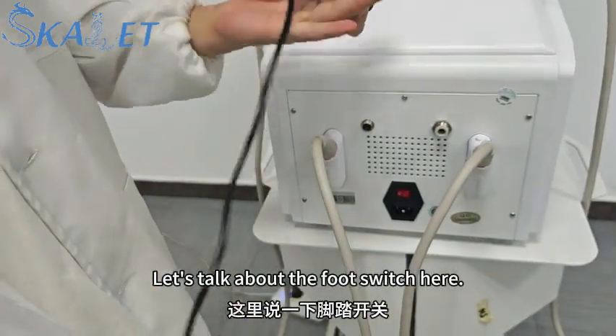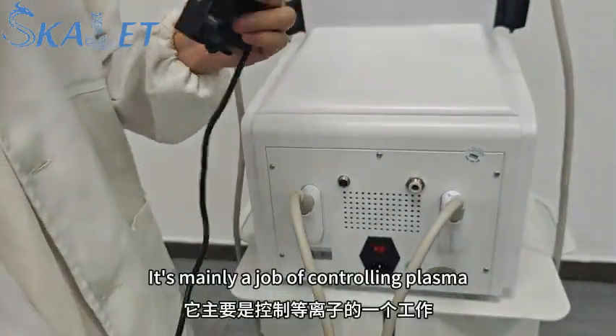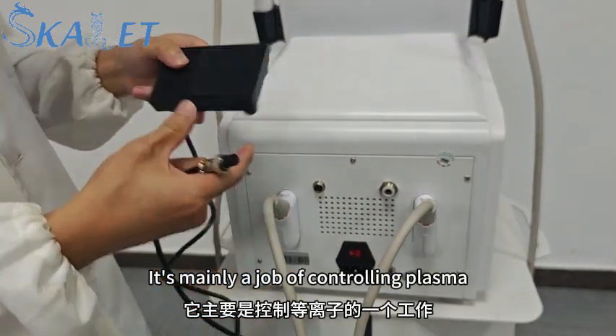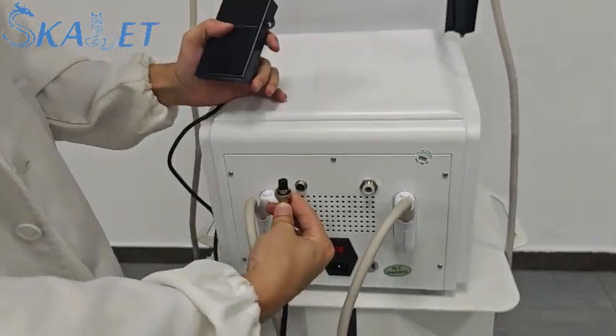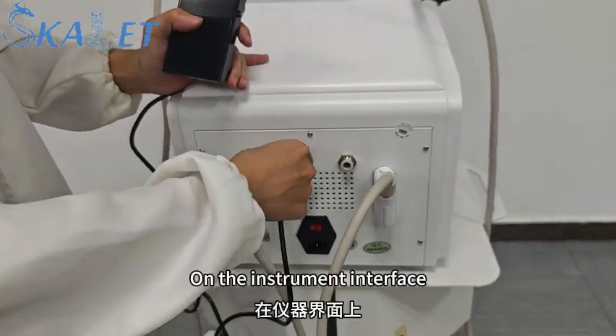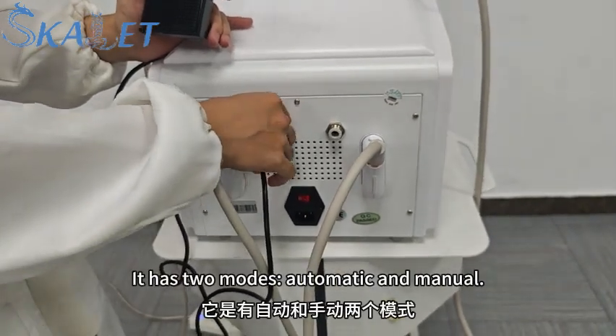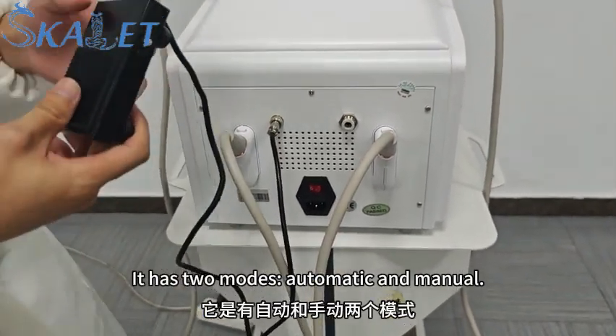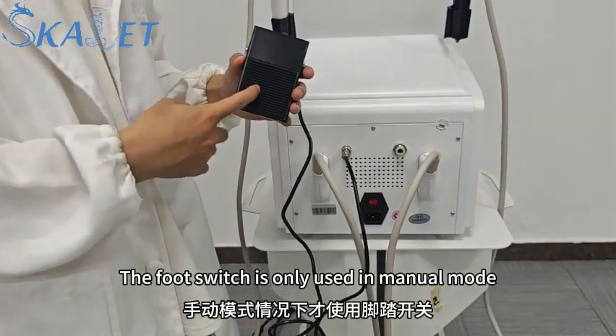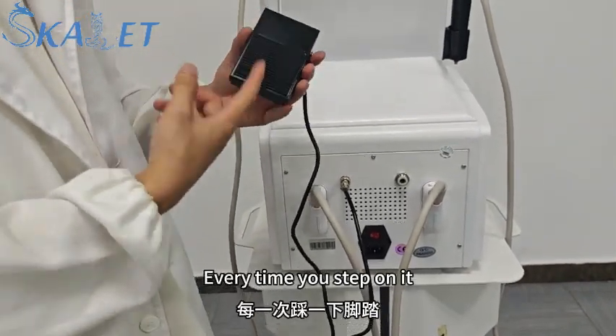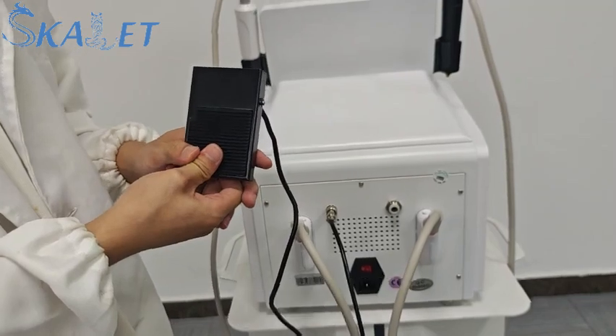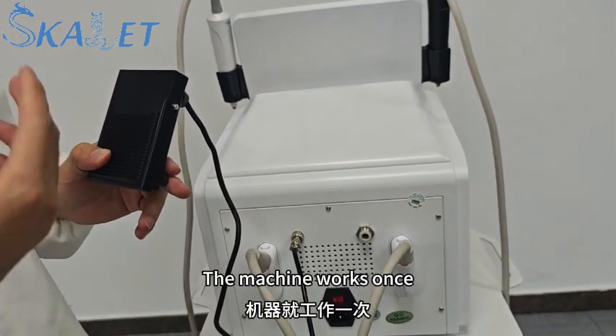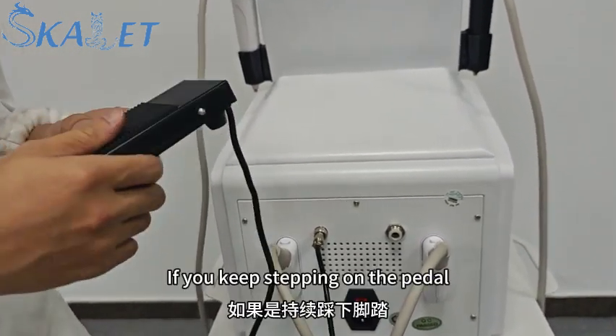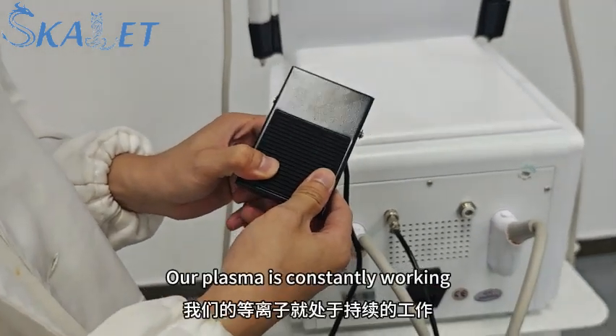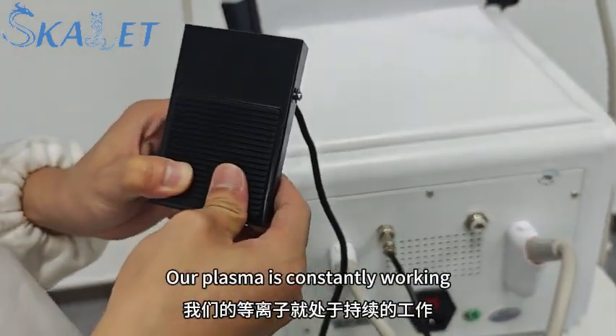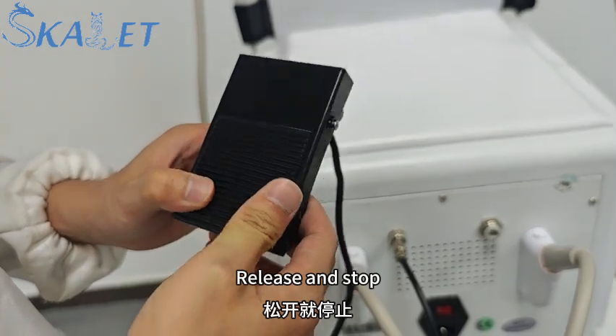Let's talk about the foot switch here. It's mainly for controlling the plasma. On the instrument interface, it has two modes, automatic and manual. The foot switch is only used in manual mode. Every time you step on it, the machine works once. If you keep stepping on the pedal, the plasma is constantly working. Release and it stops.